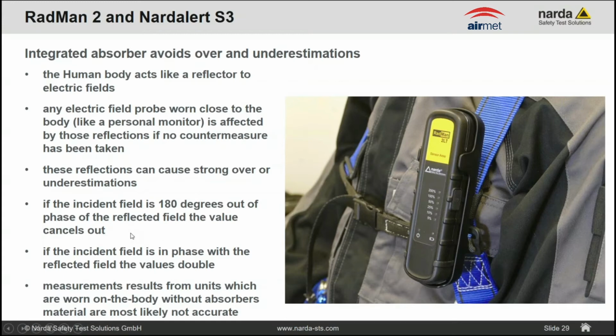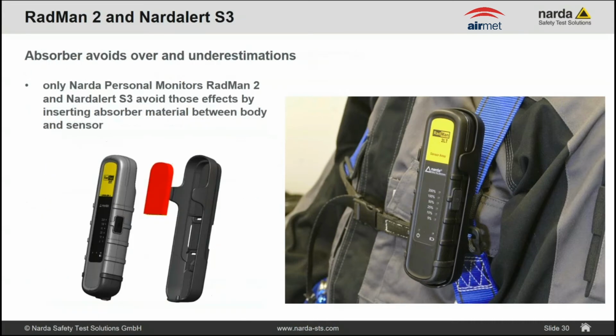So an addition of waves with a complementary, 180 degrees changed phase cancels out, or if it's in phase, the reflected field will double the value. So you want neither plus nor minus 100% measurement uncertainty. Measurement results from units worn on the body without absorber material have a very high likelihood of not being accurate. So in the holder there is foam, like the material you know from EMC shielded rooms. It is absorbing the body back reflection, and hence you will get correct readings if you use it on the body.